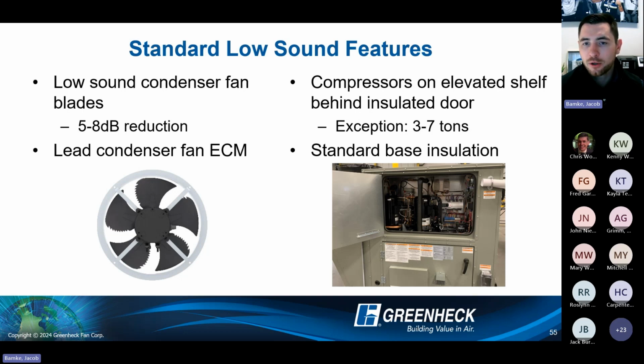And then internal, anything above 7 tons where we get to some larger equipment, we have the compressors always mounted on an elevated shelf in that insulated cabinet. And again, that includes that standard base insulation. So even if the compressors are mounted on the base, it's an inverter scroll compressor and it's insulated on that base, so you don't have any noise radiating through that base, through the ceiling into that space.